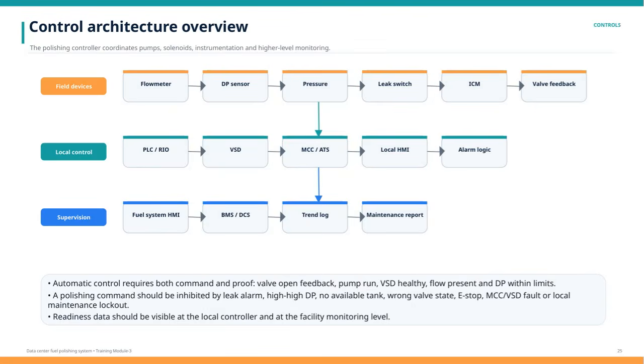The polishing controller acts as the central coordinator, managing pumps, solenoids, instrumentation, and higher-level monitoring tasks. This ensures that all components work together seamlessly. Starting with the field devices, we have essential sensors like the flow meter, differential pressure sensor, leak switch, and valve feedback systems. These provide real-time data necessary for precise control.